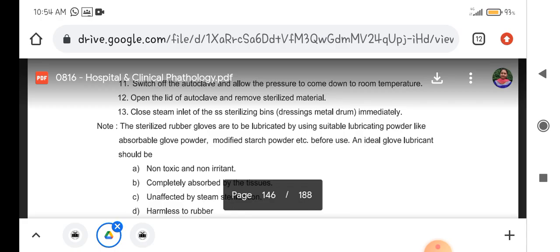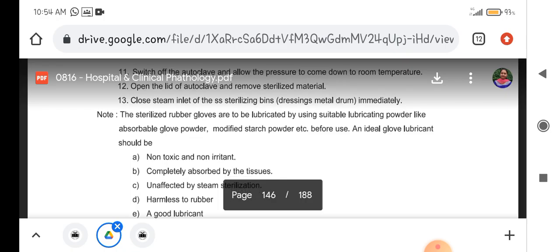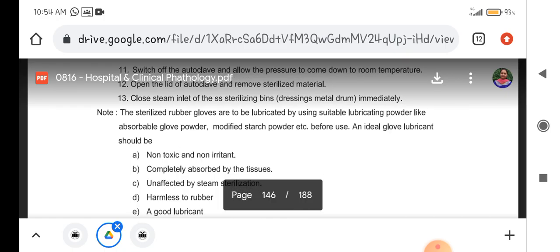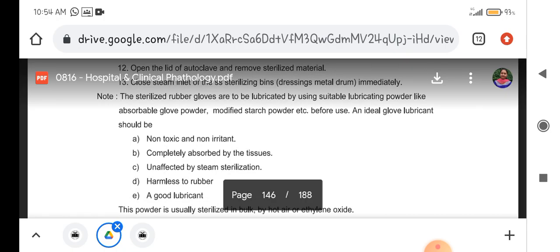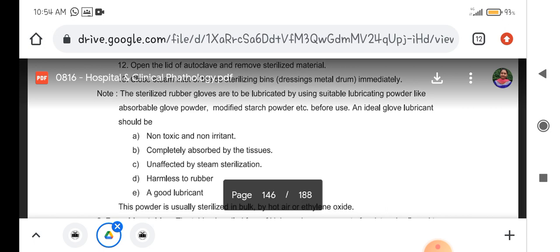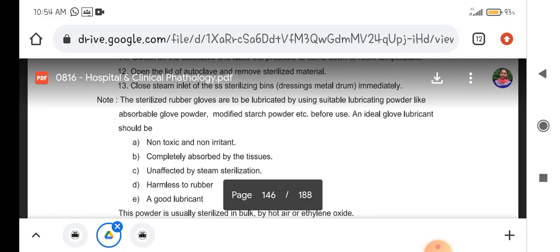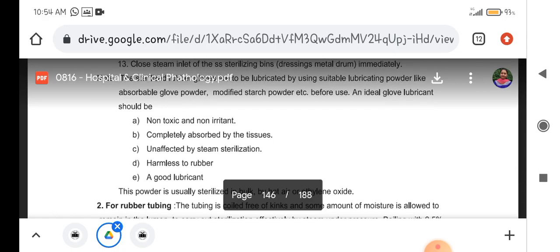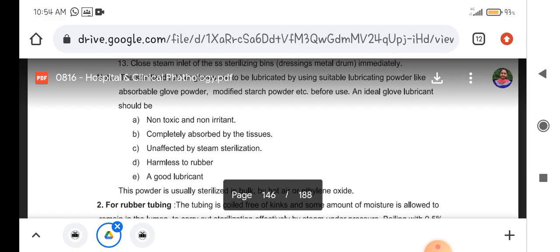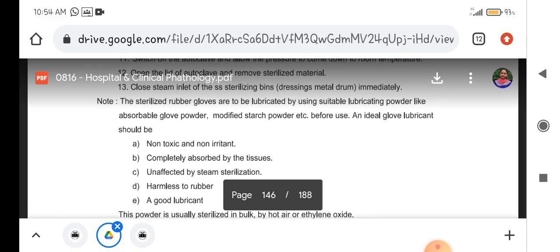Open the lid of the autoclave, remove the sterilized material, and close the steam inlet of the SS sterilizing bin immediately. The sterilized rubber gloves are to be lubricated by using a suitable lubricating powder like absorbable glove powder or modified starch powder before use. An ideal glove lubricant should be non-toxic and non-irritant, completely absorbed by the tissues, unaffected by steam sterilization, harmless to rubber, a good lubricant.